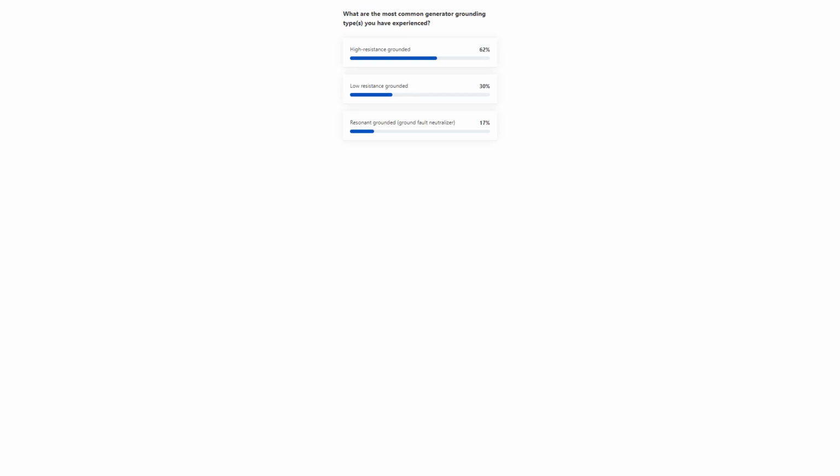Jack, please see the results from the poll question to discuss. Thank you, Monica. Yeah, actually this is expected. High resistance grounded, 62%, most of it, as I mentioned, at least what I have seen so far. Resonant grounded, I see 17.5%, and low resistance grounded. Most low resistance grounded is probably installed in an industrial setting. Correct me if I'm wrong during the Q&A. That's all. Thank you for taking the poll.